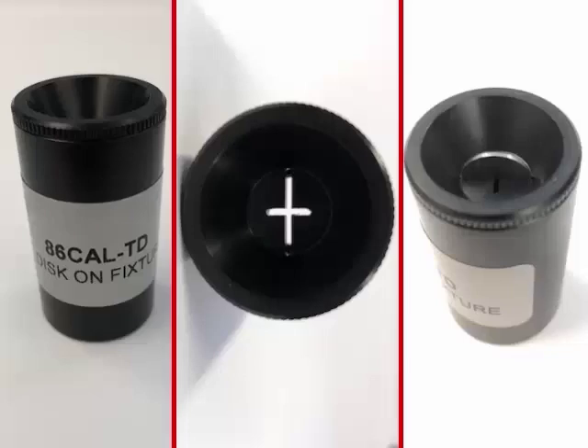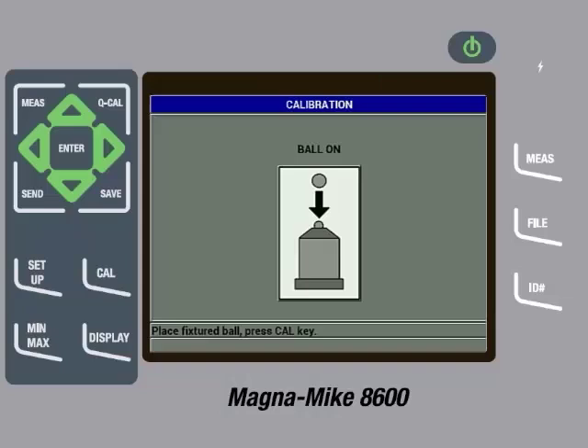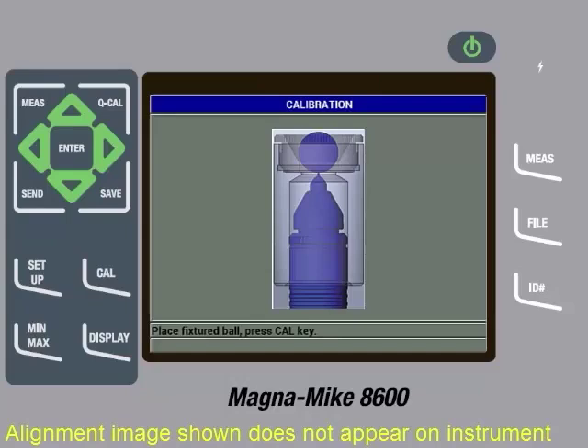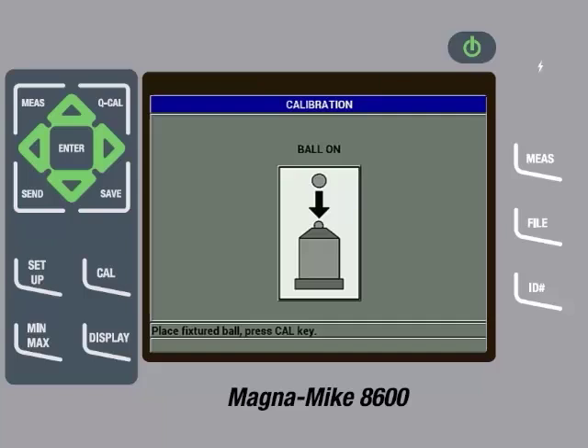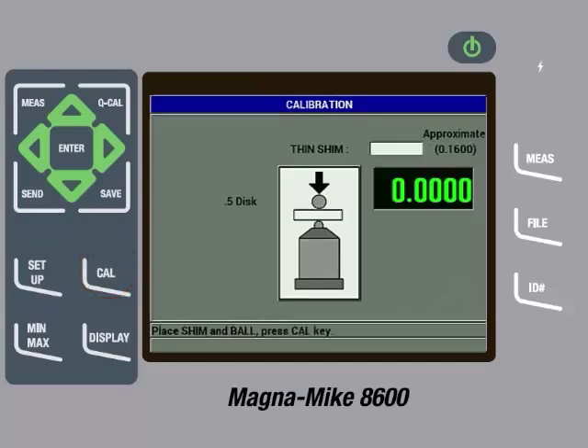To do this, take the 86 Cal-TD alignment fixture out of the calibration kit. Next, insert the disc target into the slot on the alignment fixture. If needed, force the disc through the slot a few times to ensure that it will not get caught on the sides of the slot. Then, place the disc and fixture on the probe, making sure to align the disc perpendicular to the chisel tip edge. Then, gently pull down on the sides of the fixture to ensure the disc is in contact with the probe tip, then press the Cal key. After processing, the gauge will display a 0 value. We can now remove the disc and fixture.